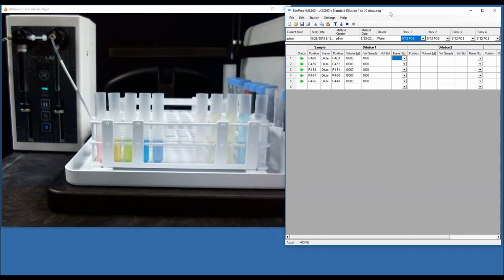The only other maintenance really is trying to keep the system clean. And of course, the peristaltic pump tubing on the back will wear out. That again, we recommend a yearly maintenance. As far as the syringes go, if you do start to see buildup on them, they're really easy to take out and clean. There's actually a syringe removal button in the software that makes it really easy to take them off. And typically with the Hamilton syringes, all you have to do is open them up and wipe them out, and then you put them back together and you're good. So maintenance is really very limited.